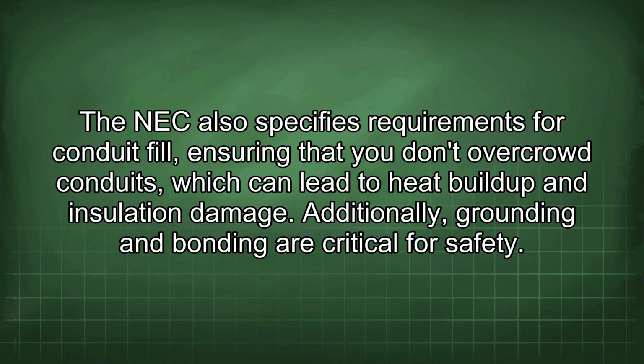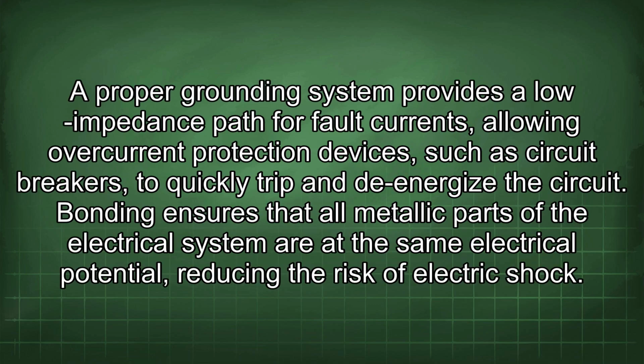Additionally, grounding and bonding are critical for safety. A proper grounding system provides a low impedance path for fault currents, allowing overcurrent protection devices, such as circuit breakers, to quickly trip and de-energize the circuit. Bonding ensures that all metallic parts of the electrical system are at the same electrical potential, reducing the risk of electric shock.